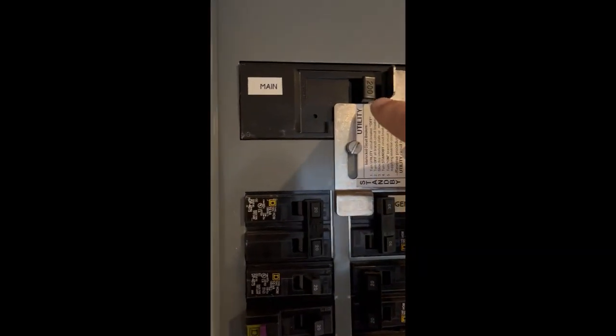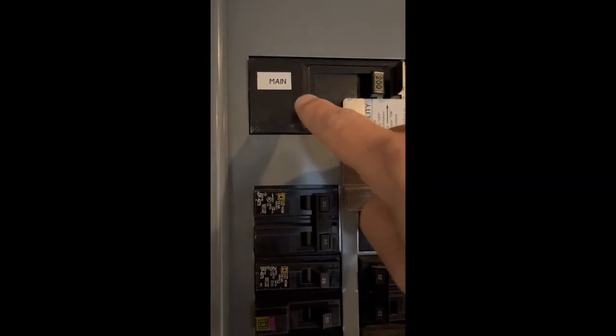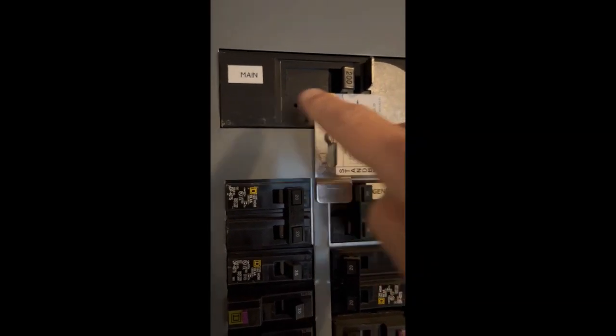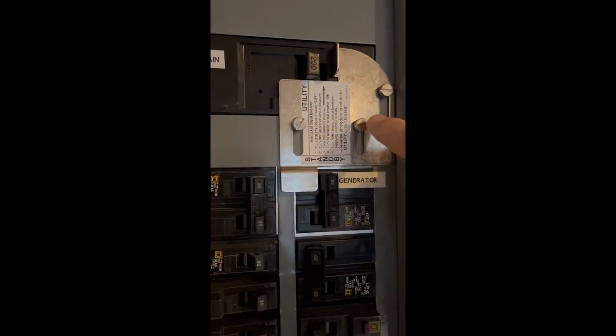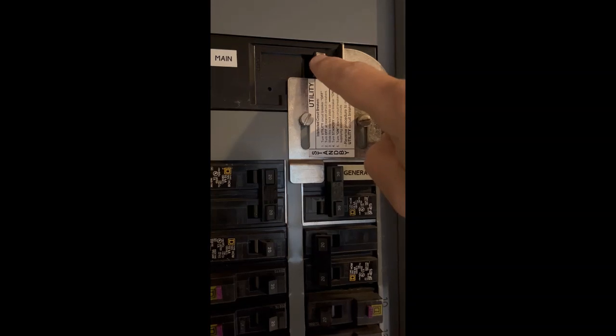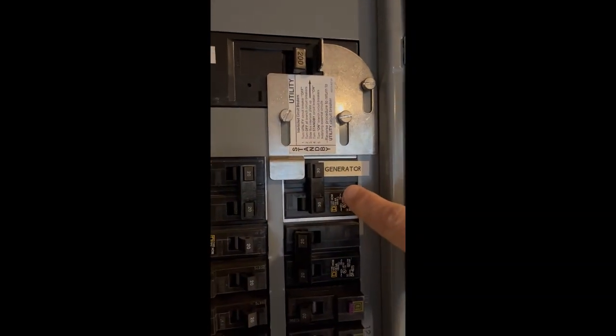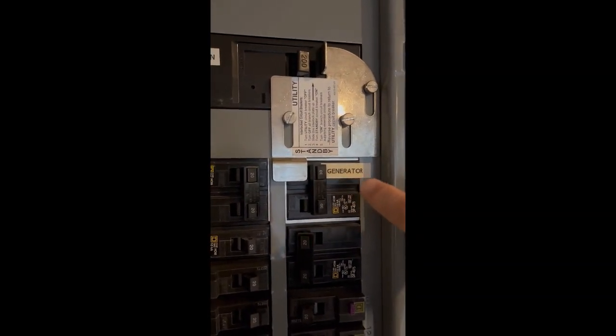Here you'll see the main circuit breaker. Step 1, you're going to flip this to the left to turn all the electricity off to the house. There's a safety here that helps prevent you from having this breaker and the generator breaker in the on position at the same time.